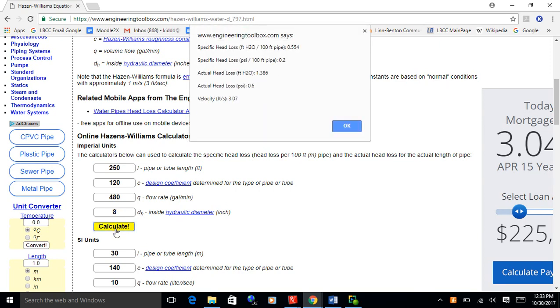Yeah, 1.38, 1.25. Yeah, okay. This thing's coming just a little bit higher than what we're getting. It's fine. It's probably good, right? Yeah, generally speaking, it's okay to come in a little high. You want to be a little careful on that if you're doing pumping systems, because you don't want to over-design a pump too bad, because you can cavitate. You want a pump that fits your system. You don't want to oversize it too much. But this is plenty good, so far anyway.